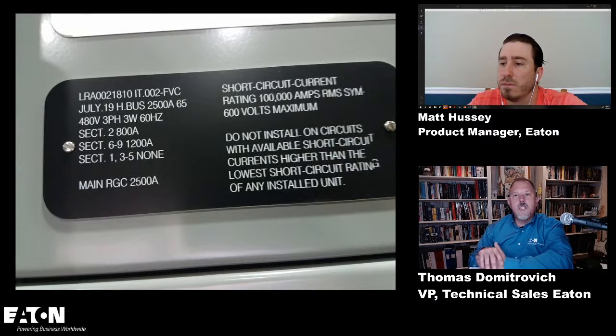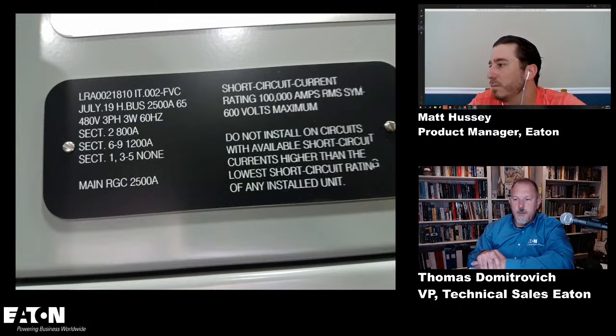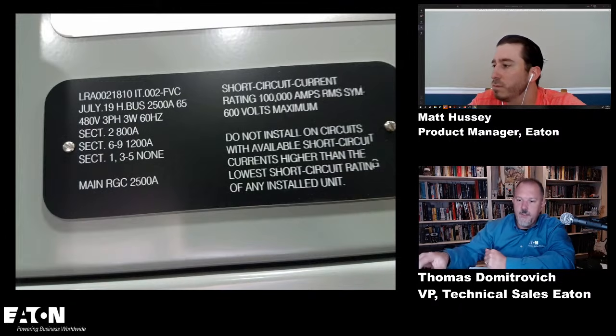So it says that this is a 2500 amp main, so that's a 2500 amp piece of equipment. What's the largest amp rating MCC that's made? You'll see typically around 3,000, or in our case, we do 3,200 amp. So I couldn't get a 4,000 amp MCC. So no. All right. Okay, so 3200 amp MCC. This is a 2500 amp MCC.